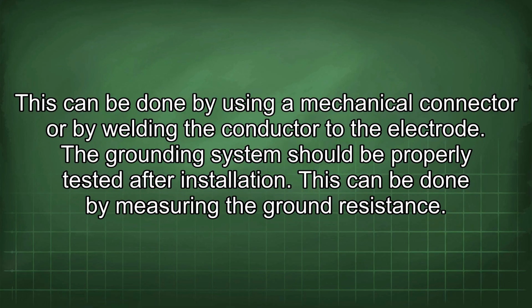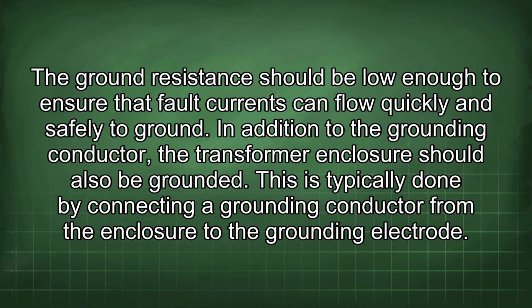The grounding system should be properly tested after installation. This can be done by measuring the ground resistance. The ground resistance should be low enough to ensure that fault currents can flow quickly and safely to ground. In addition to the grounding conductor, the transformer enclosure should also be grounded. This is typically done by connecting a grounding conductor from the enclosure to the grounding electrode.